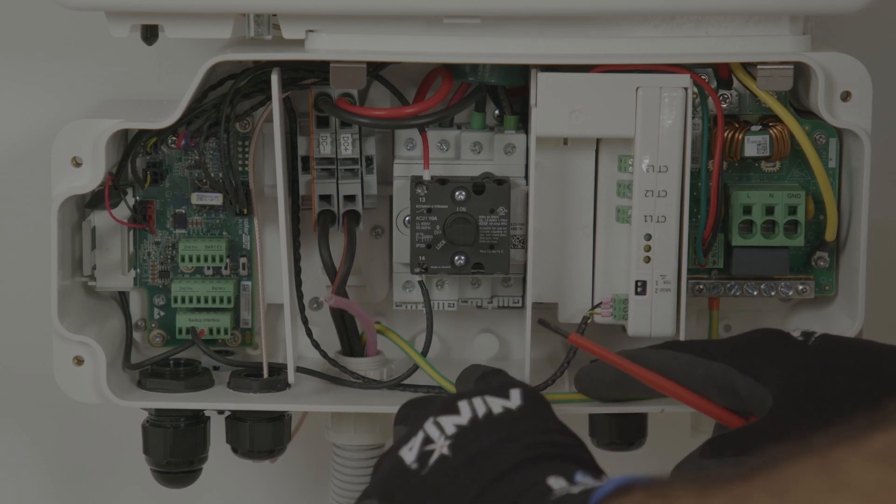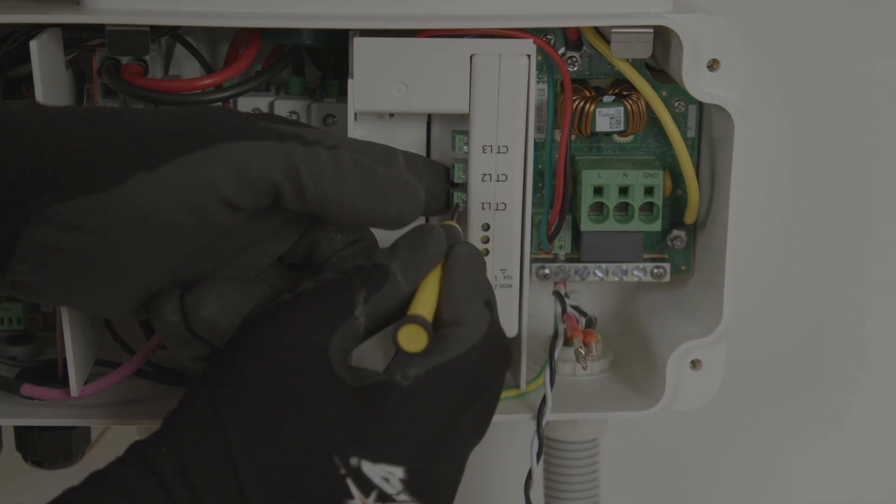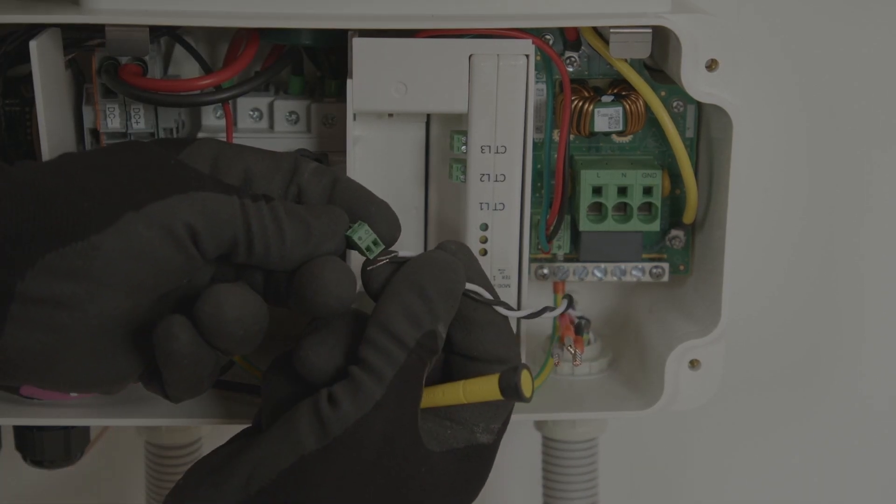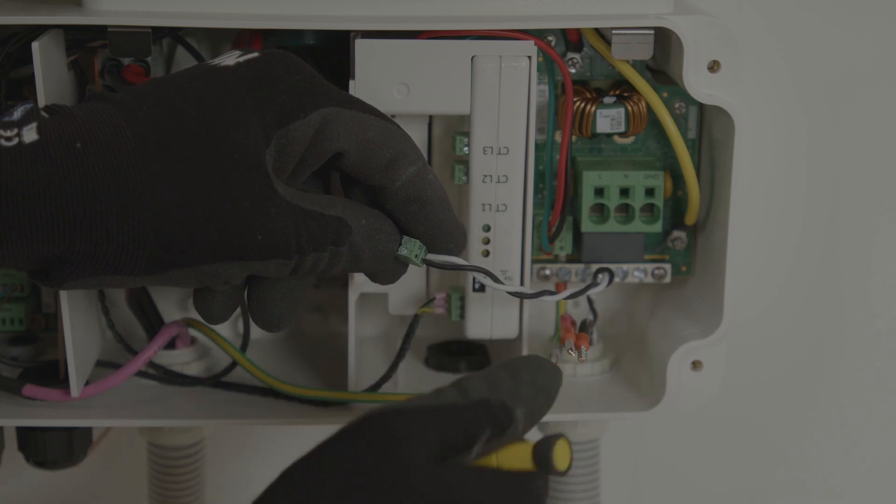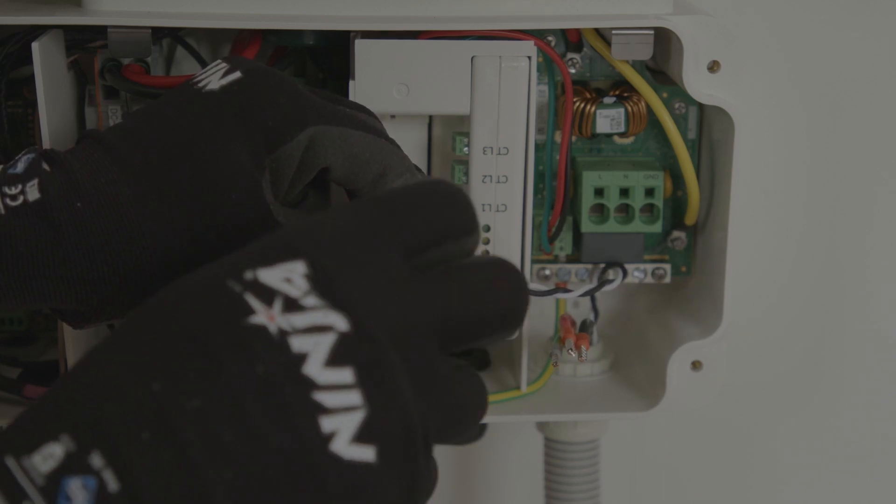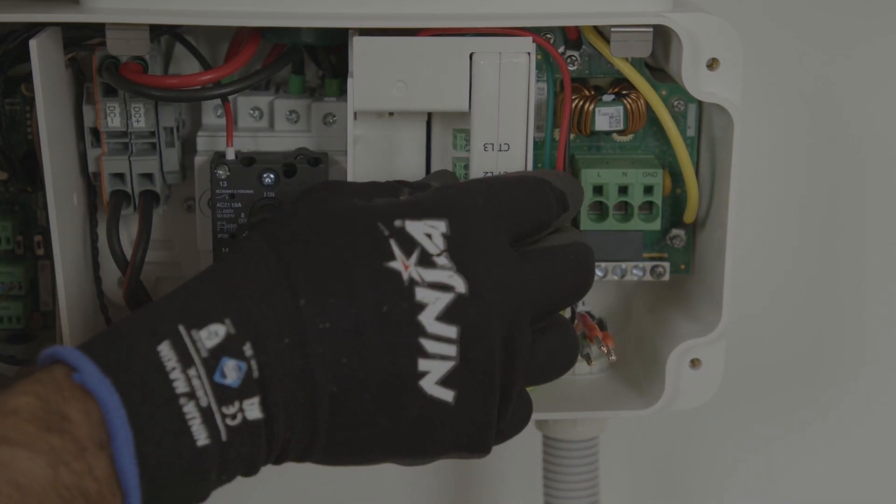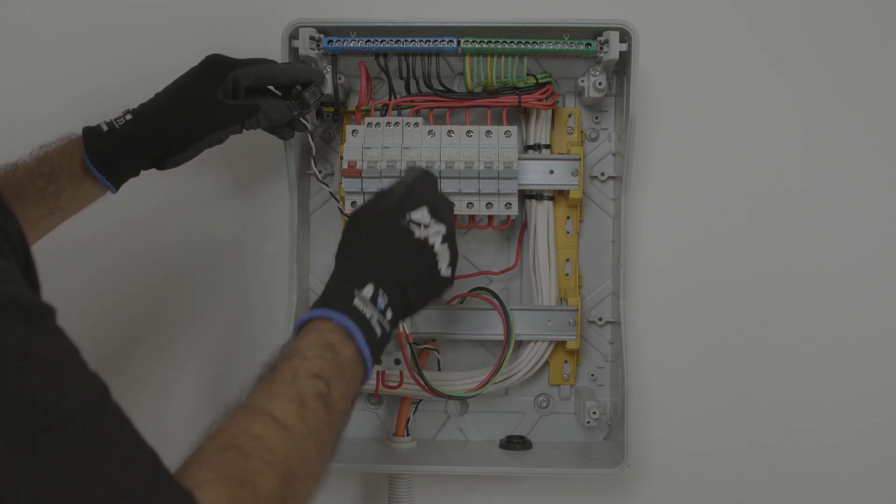The Energy Hub also has the inbuilt Modbus meter. All that is required is for the CT connection to be wired. Simply fit the CT onto the incoming connection from the grid with the arrow pointing towards the grid.